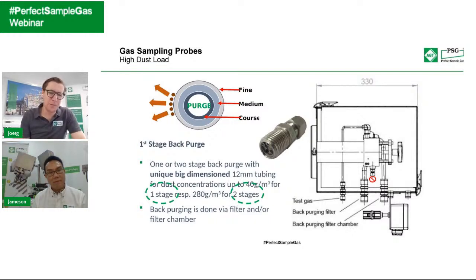And this is also one option here, which is the pressure reduction valve, the technology we wanted to introduce here, because when you have back purging, you might see the situation that the probe itself is getting clogged and you have to back purge quite a lot. This back purging can also bring pressure to your analyzer system. And we always have to consider that on the probe we have a connection to the heated sample line, to avoid cold spots. Maybe, Jameson, also part of our quick fix, something we will discuss on the heated sample lines.